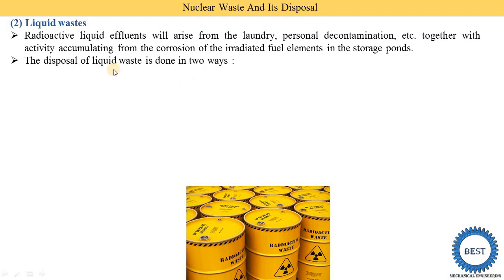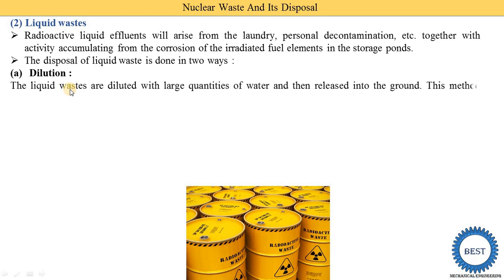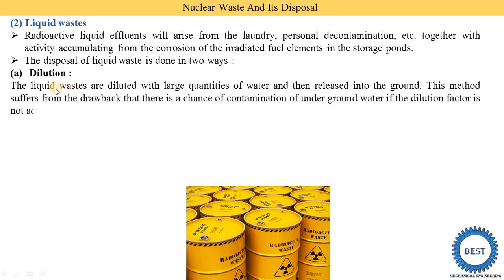The disposal of liquid waste is done in two ways. The first is dilution — the liquid waste is mixed with a large quantity of water so its intensity is reduced, and then released into the ground. This method suffers from the drawback that there is a chance of contamination of underground water if the dilution factor is not adequate — meaning if sufficient water is not provided, the dilution factor is too low, and underground water may become contaminated with radioactive material, which is harmful to humans and the environment.